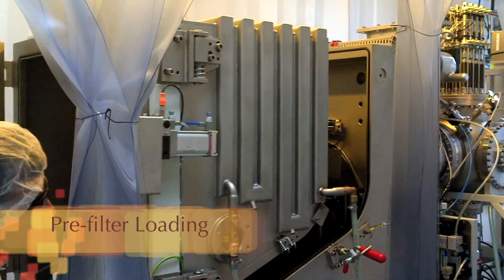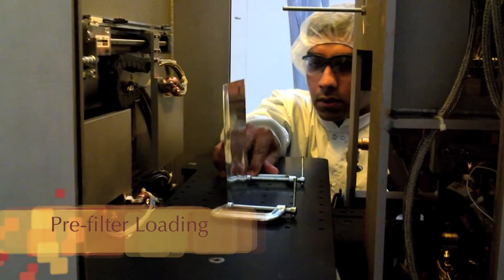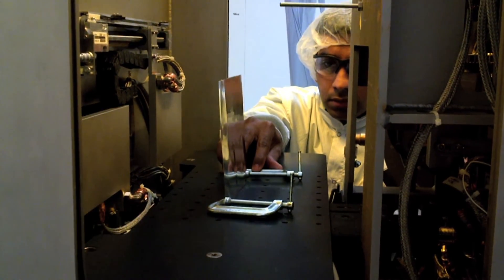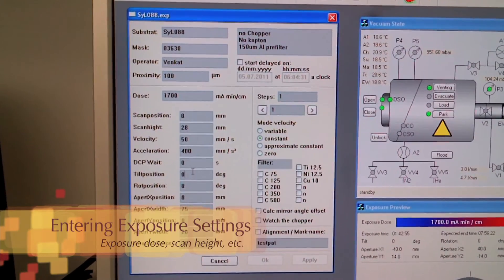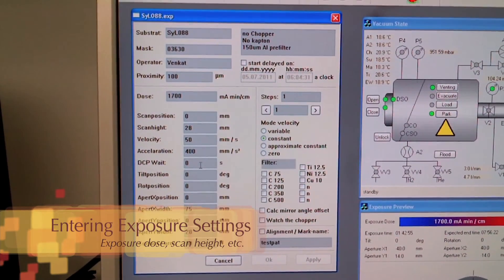Once the dose is calculated and the sample loaded, the beamline equipment are set to the calculated positions and the pre-filter is loaded inside the scanner. Using the dedicated scanner software, the exposure settings are entered.